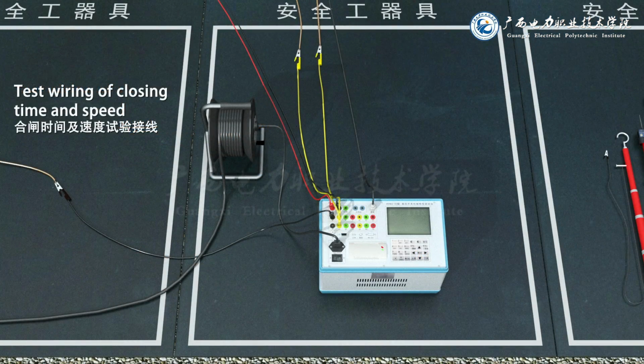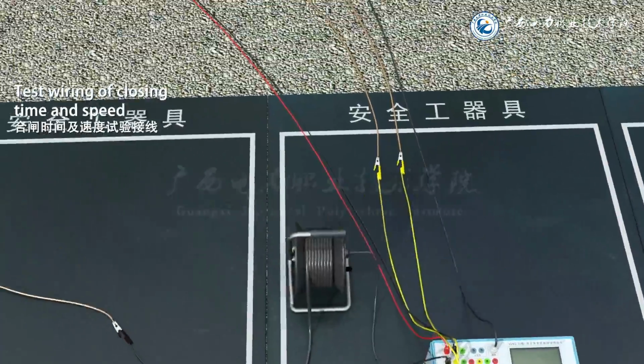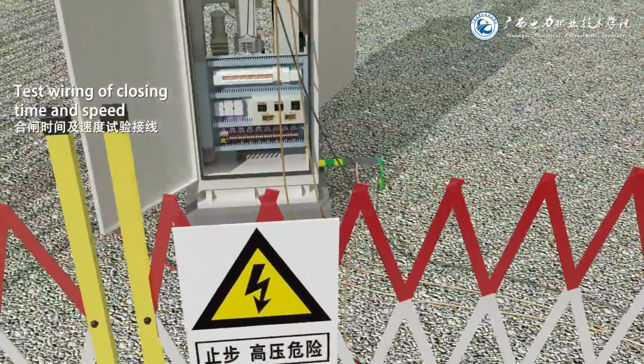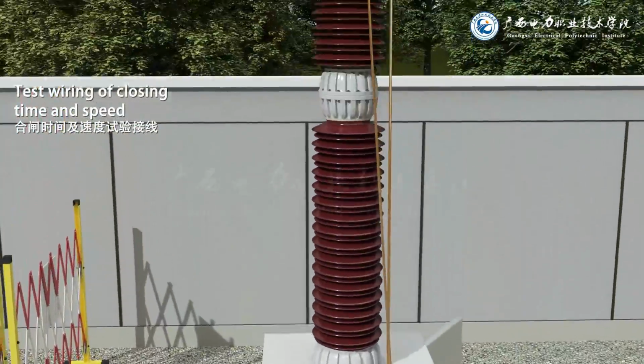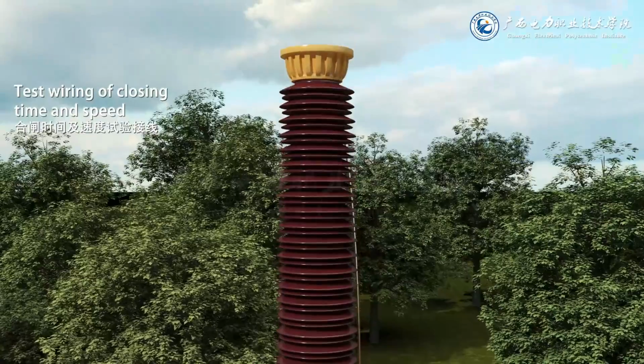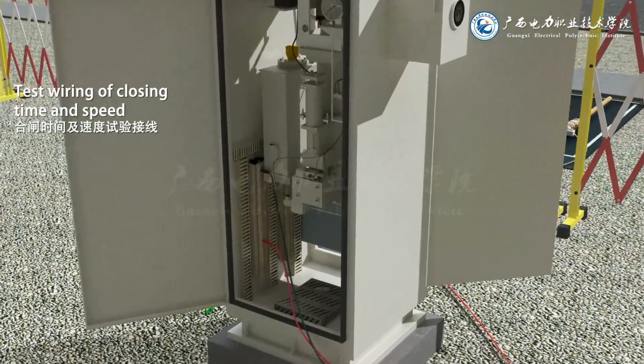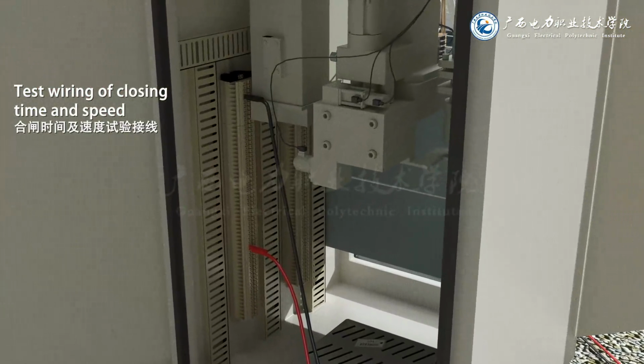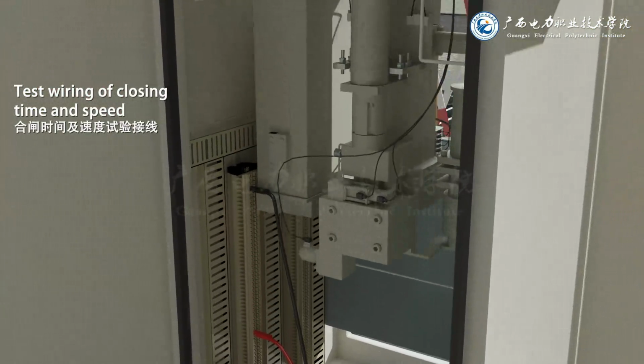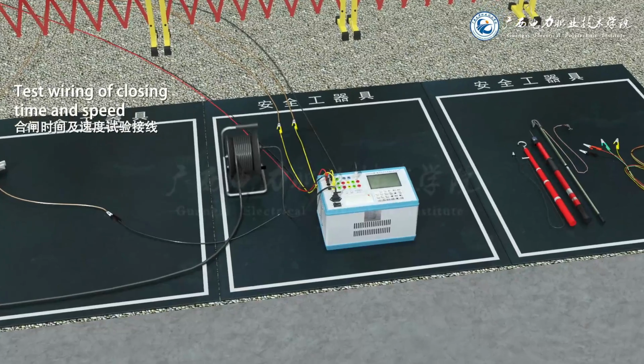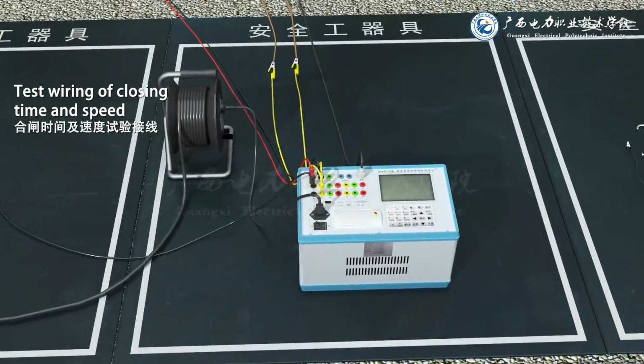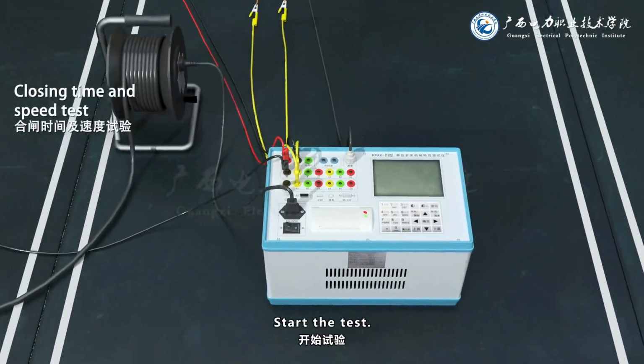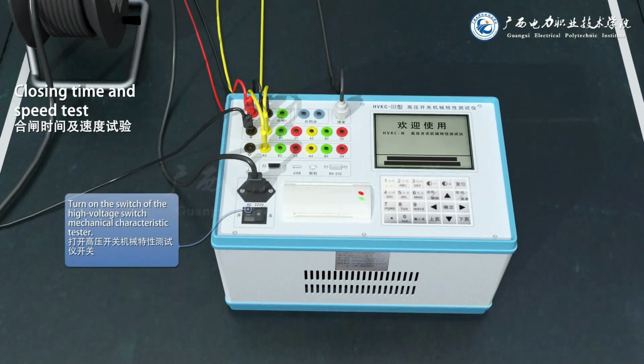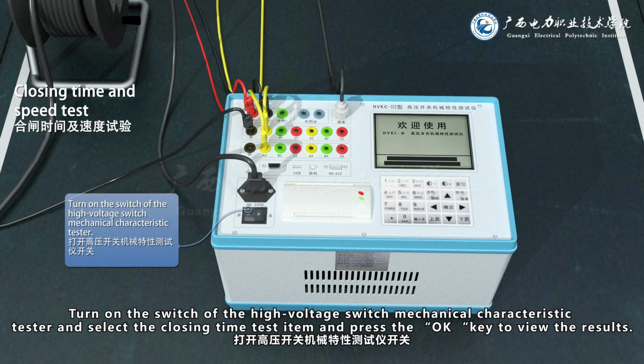Test wiring of closing time and speed. Start the test. Turn on the switch of the high voltage switch mechanical characteristic tester and select the closing time test item and press the OK key to view the results.